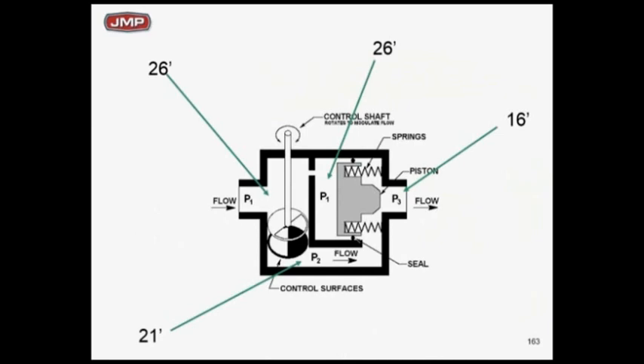The idea is that the spring load is going to maintain a constant differential across the two-way valve, P1, P2. You can now pick your pressure independent control valves on GPM. You don't even have to worry about Cv. You can pick your control valves just on gallons per minute. What GPM is it? What valve do I need? You don't worry about valve authority. The pressure independent control valve will take care of that for you.